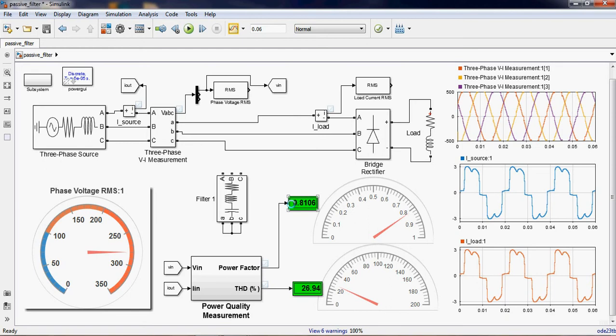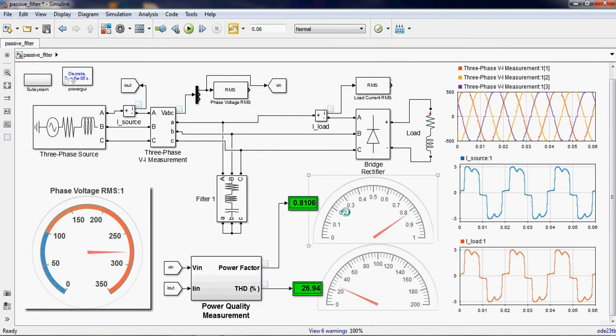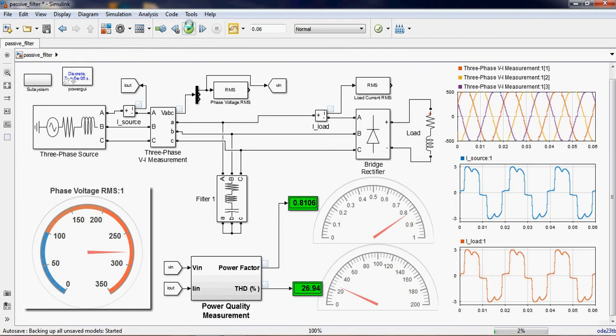And the power factor is near about 0.51, is available in meters. Now you just connect the filter to the supply where you can say grid three-phase. Now what is the performance or how the current is going to improve due to this filter? That we will see running the simulation.